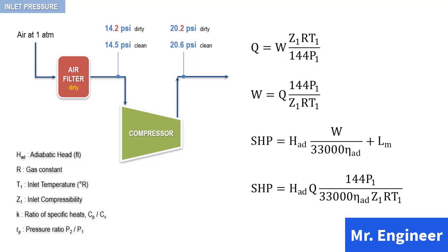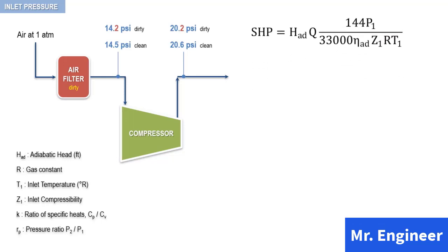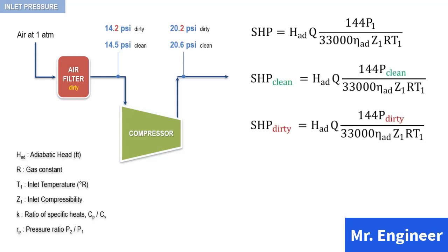This last equation is not strictly valid, because shaft horsepower is composed of gas horsepower and mechanical losses. As a rule of thumb, for centrifugal compressors, the mechanical losses are approximately constant for a given speed, but are in general a small part of the total horsepower. Therefore, ignoring mechanical losses will usually yield a useful approximation. Starting from the general horsepower equation, dividing SHP dirty by SHP clean yields the following useful relationship: shaft horsepower is proportional to the inlet pressure.